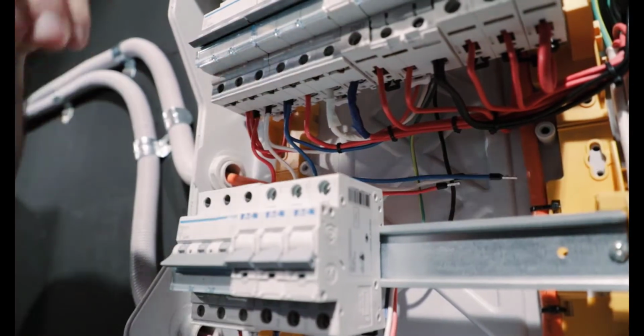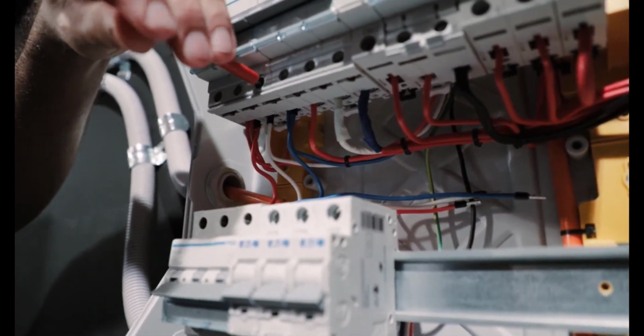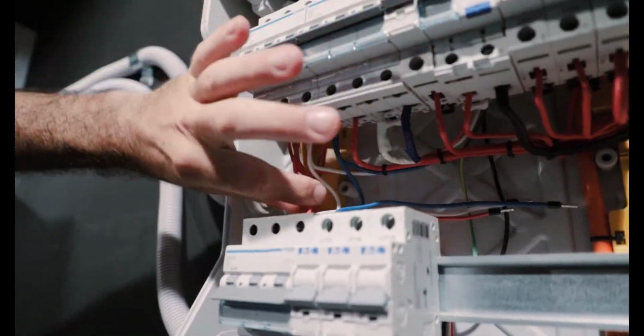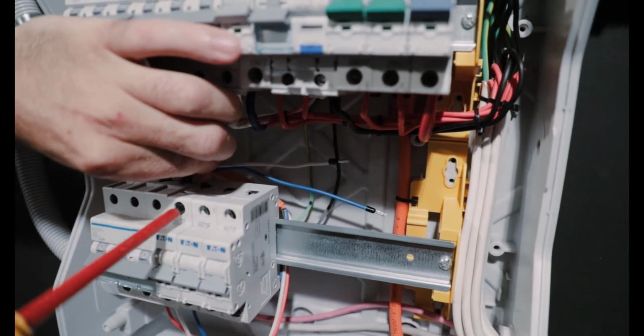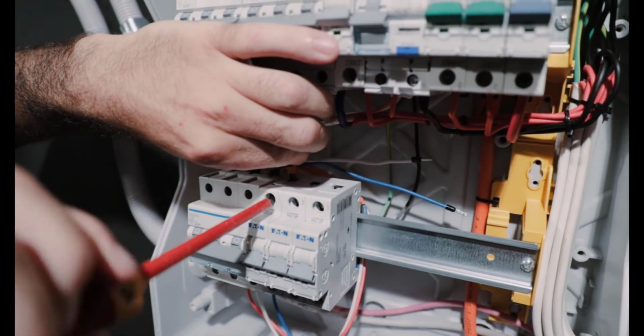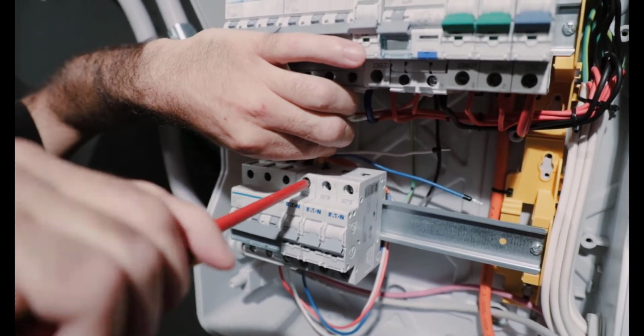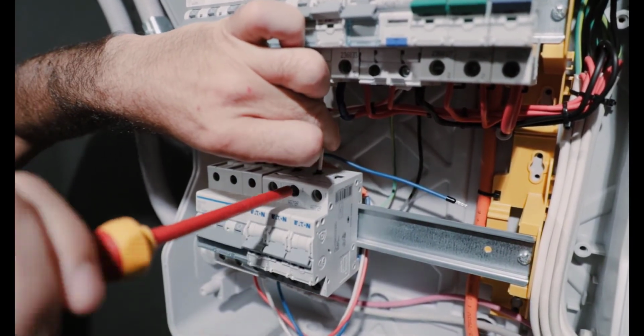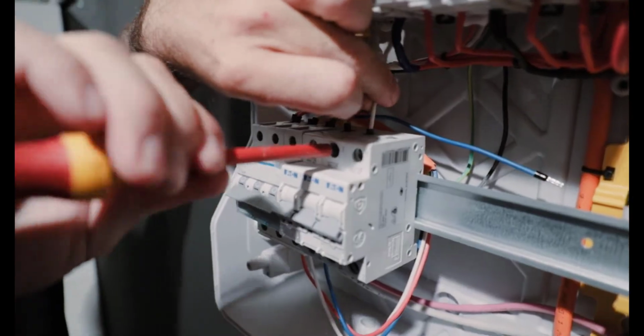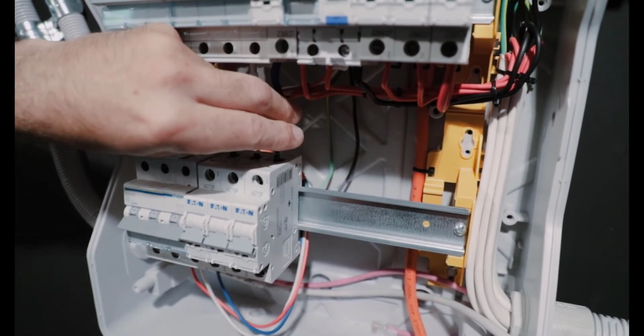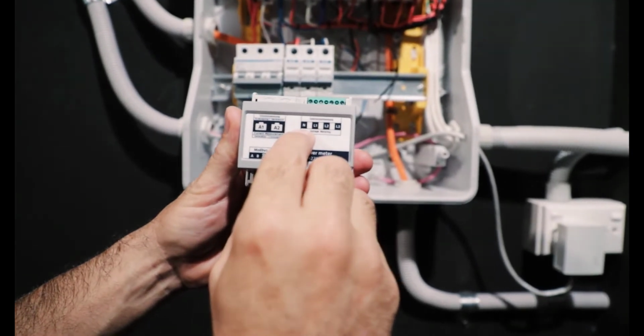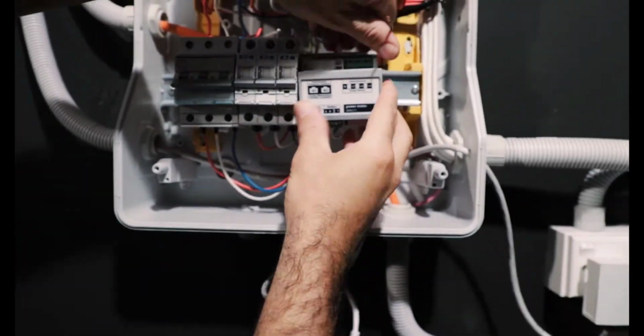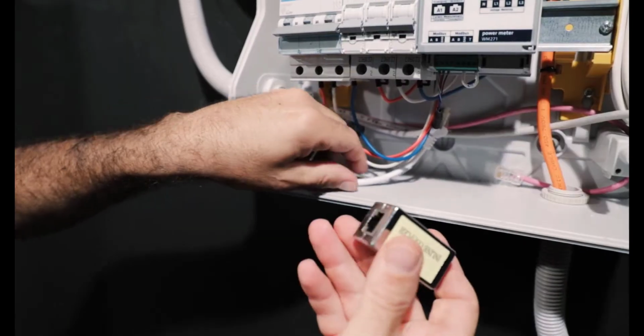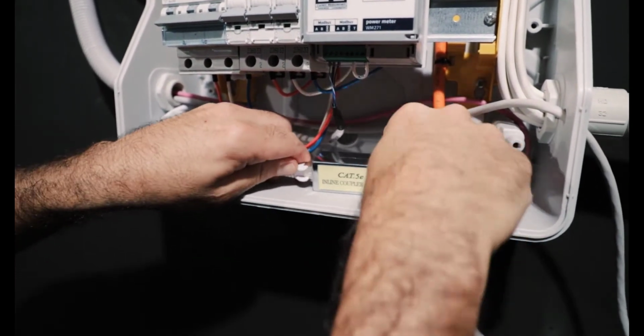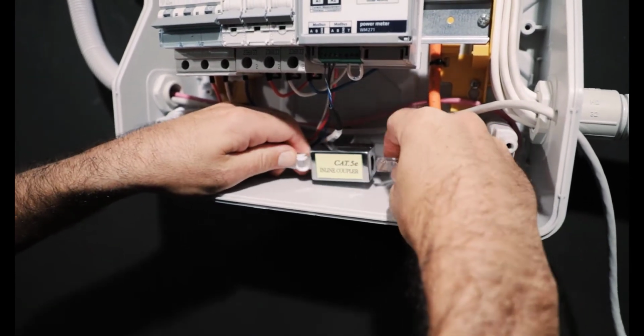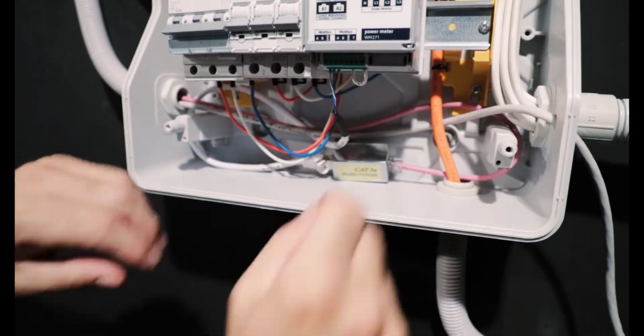What is very important when connecting all of this up is to ensure that the phases are correct. So the phases for the metering, the phases for the CTs, and the phases for the sonnenBatterie, they all need to be consistent. Using color-coded cabling or the correct harmonized cabling is the simplest way to do this. Unfortunately, I have seen an awful lot of boards where everything active is red. So this, again, 3-phase meter, neutral, L1, L2, L3. Okay, done. And then once more, we connect our Modbus connection so that the meter can happily communicate with the sonnenBatterie system.